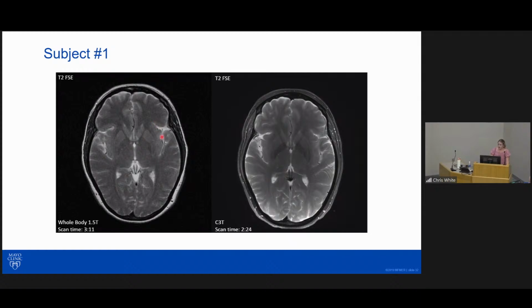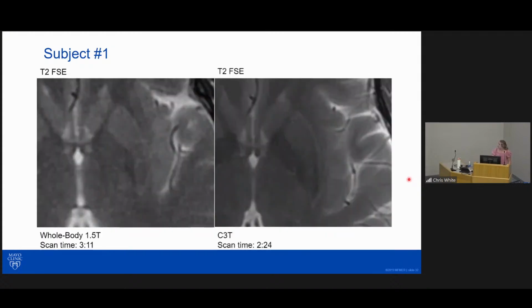This slide shows the T2 fast spin echo images from subject 1. The whole body 1.5T image is shown on the left with a scan time of 3 minutes, 11 seconds, and the compact 3T image is on the right with a scan time of 2 minutes, 24 seconds. There's an increase in the visual signal to noise ratio and overall image quality on the compact 3T image compared to the 1.5T image. And here's a zoomed in version of those same slides so you can appreciate that increase in image quality.